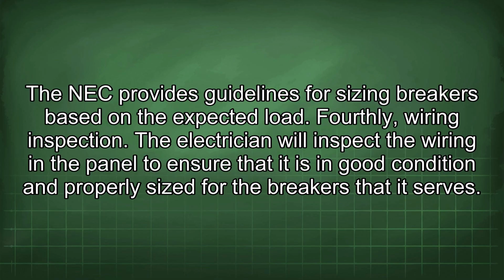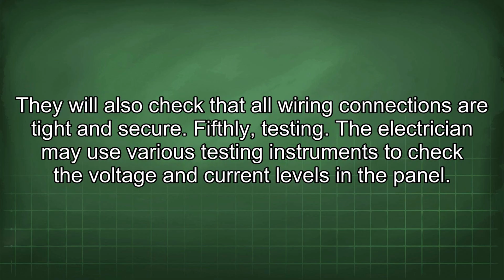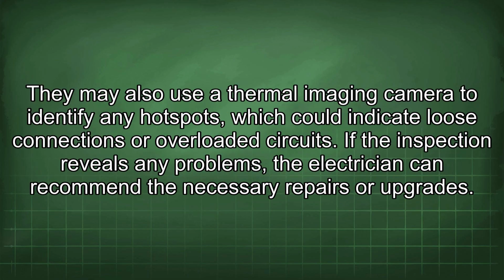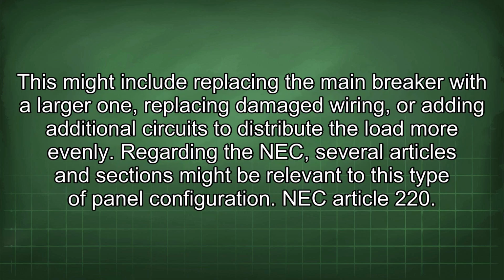Fourthly, wiring inspection. The electrician will inspect the wiring in the panel to ensure that it is in good condition and properly sized for the breakers that it serves. They will also check that all wiring connections are tight and secure. Fifthly, testing. The electrician may use various testing instruments to check the voltage and current levels in the panel. They may also use a thermal imaging camera to identify any hotspots, which could indicate loose connections or overloaded circuits. If the inspection reveals any problems, the electrician can recommend the necessary repairs or upgrades. This might include replacing the main breaker with a larger one, replacing damaged wiring, or adding additional circuits to distribute the load more evenly.